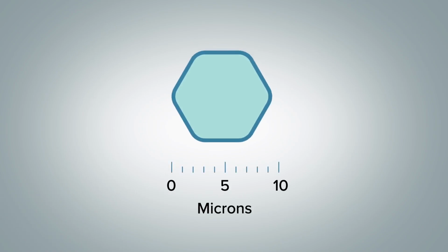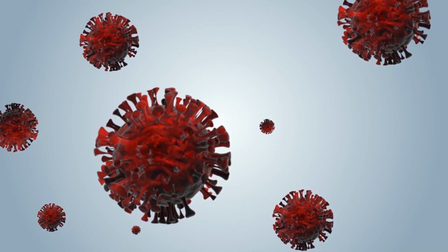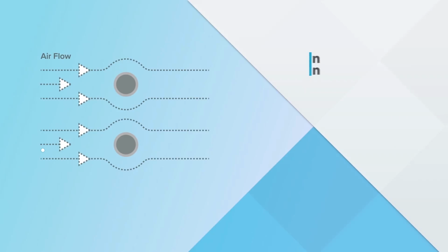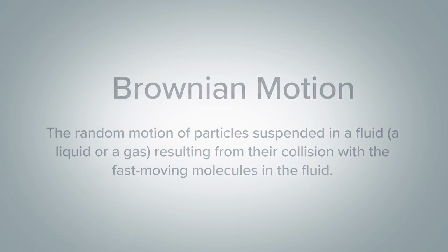As we get down to ultra-fine particles under 0.3 microns, the particles or microorganisms start behaving differently. They take on a gaseous characteristic where they begin moving all around and bumping into each other. So in addition to traveling horizontally within the airstream, they also have a vertical movement and have a high probability of hitting and being captured by the filter media. In physics, this is called Brownian motion, and this filtration process is called diffusion.